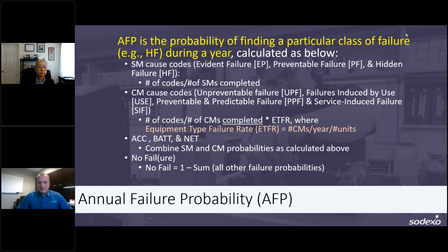So the ACC, BAT, and NET are calculated both and added up. To go back to corrective maintenance failure, a quick example is if you have 500 repairs on infusion pumps and you have 1,000 devices, your failure rate for a 12-month period would be 50%. So no failure or no problem found is basically the difference between all failure probabilities, 1 minus the sum of all failure probabilities.